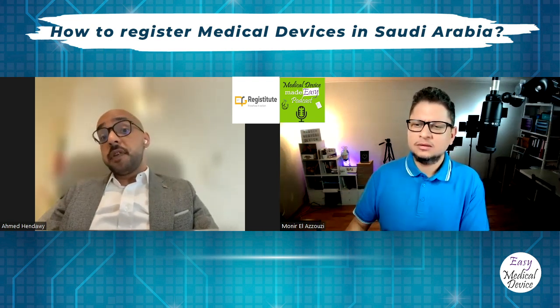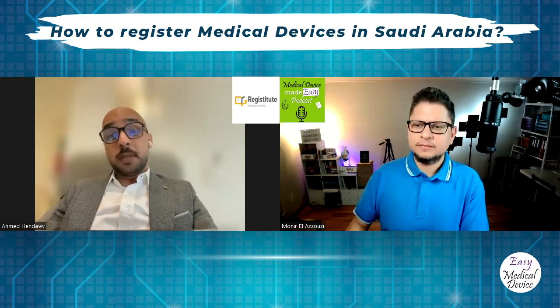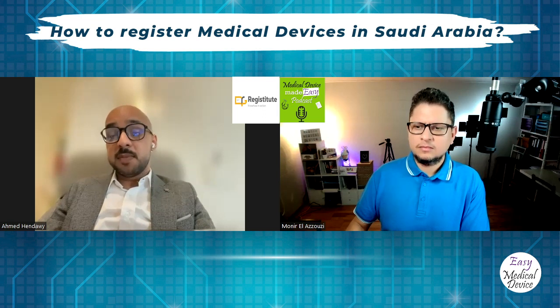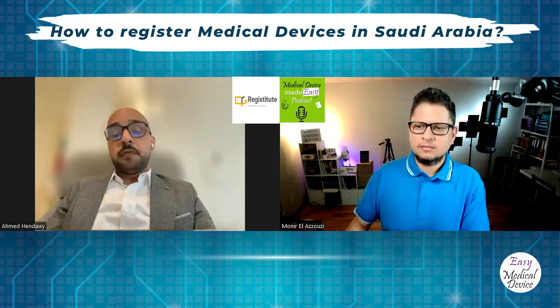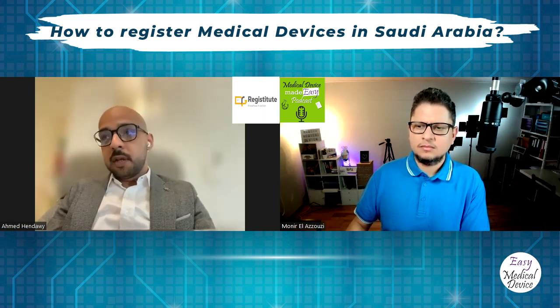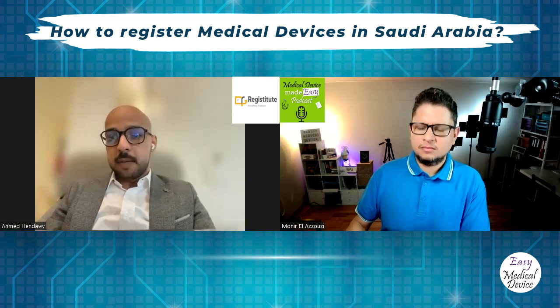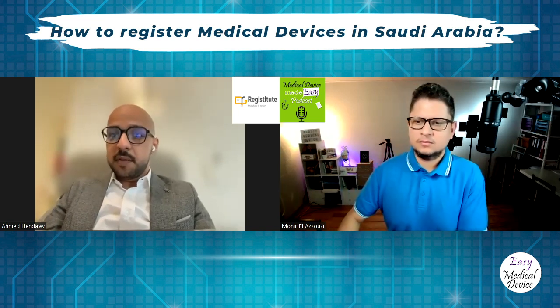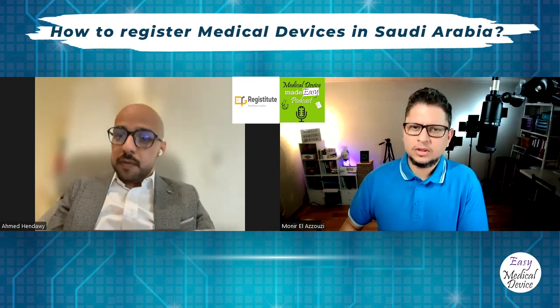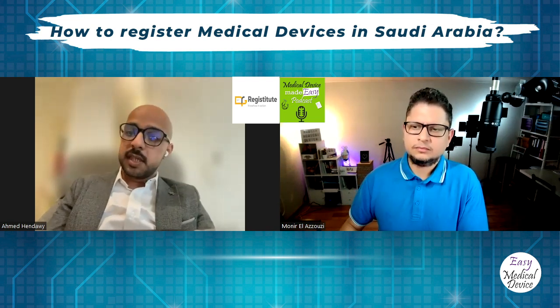It's a maximum of 3 years, but it also depends on the approval certificate in the application. Sometimes, for example, if you have a CE mark that's valid only until next December, then you'll receive the SFDA certificate until December. So then you have to renew once you have the new CE certificate.